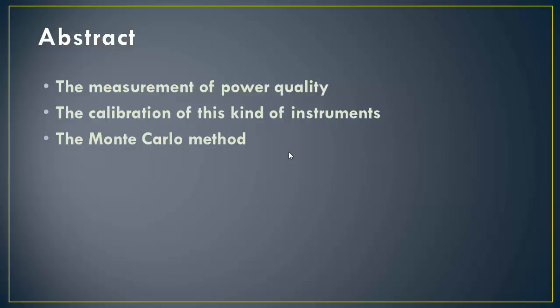concerned. This paper proposes an innovative procedure based on the Monte Carlo method, starting from the determination of the probability density function of the uncertainty contribution of every device from the signal input stage to the analog to digital conversion stage. This procedure estimates the probability density function of the measurement result and the measurement standard uncertainty as the standard deviation associated with this function. The results of the experimental work done on a prototype of a power quality measurement instrument are reported.